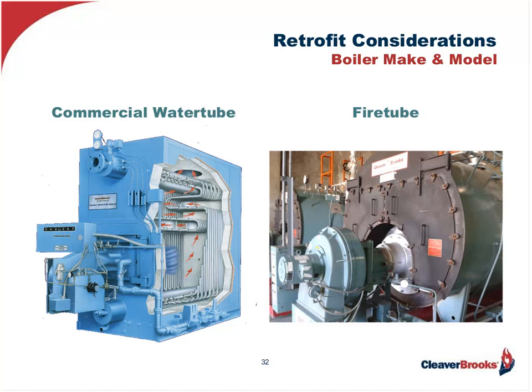There's also the possibility of load reduction, wherein the burner needs to be downsized. In this case, we need to assure ourselves that circulation in the boiler is not compromised and that we will not have the additional problem of flue gas condensing in the boiler or in its stack. We've got to contact the manufacturer to find out what this reduction in input would do to that boiler, because flue gas condensation is corrosive and will soon manifest itself in metal corrosion of those surfaces coming in contact with it.